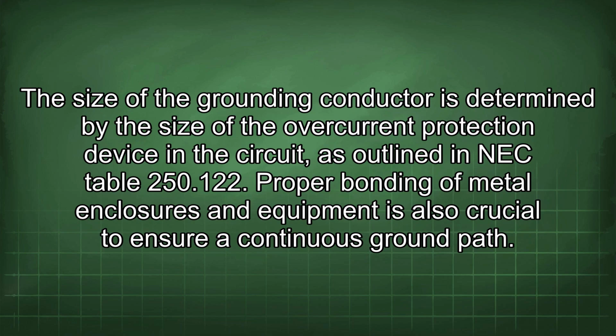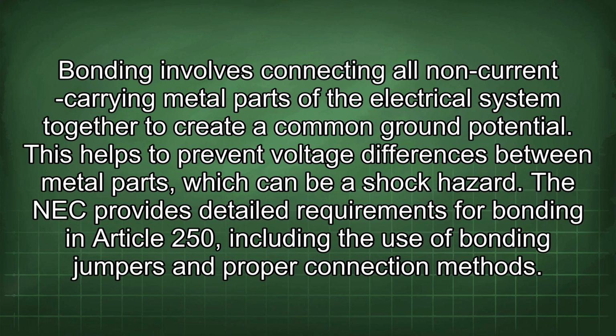The size of the grounding conductor is determined by the size of the overcurrent protection device in the circuit, as outlined in NEC Table 250.122. Proper bonding of metal enclosures and equipment is also crucial to ensure a continuous ground path. Bonding involves connecting all non-current carrying metal parts of the electrical system together to create a common ground potential.